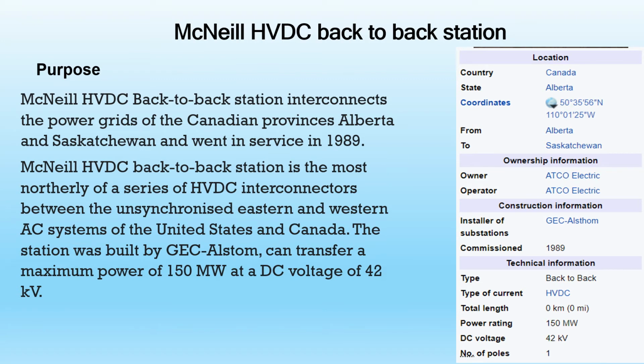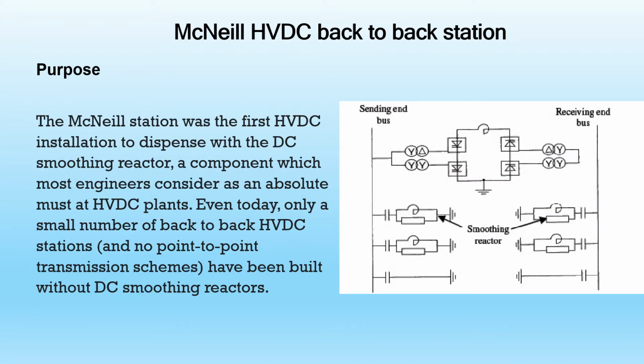The station was built by GEC Alstom and can transfer a maximum power of 150 MW at a DC voltage of 42 kV. The McNeill station was the first HVDC installation to dispense with the DC smoothing reactor, a component which most engineers consider an absolute must at an HVDC plant. Even today, only a small number of back-to-back HVDC stations have been built without DC reactors.